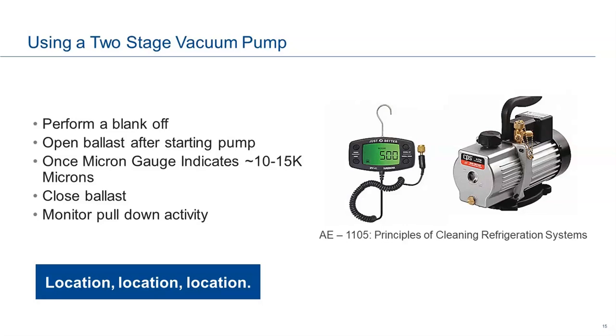I know a lot of guys nowadays are pulling down 200-300 microns. It's a different world out there. We were always told if you pulled it down too low, you'd break the oil down, but that's just a myth. It's not the case at all.